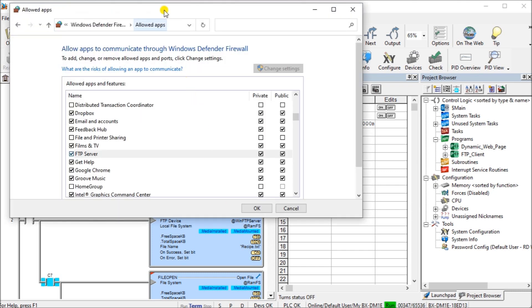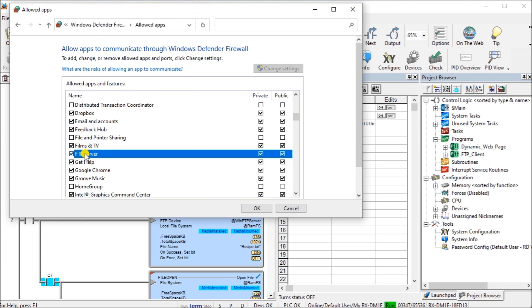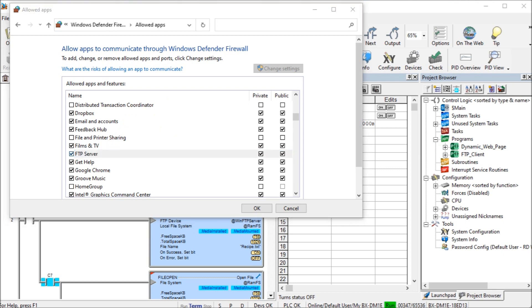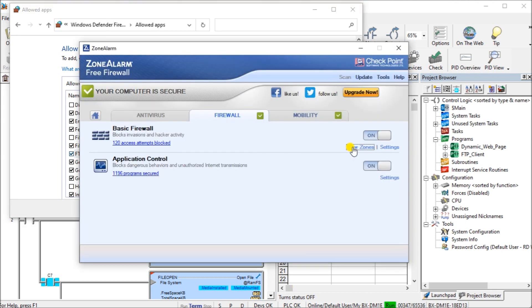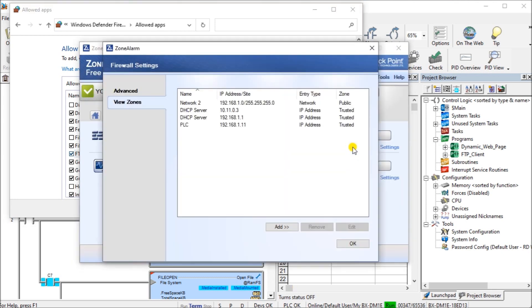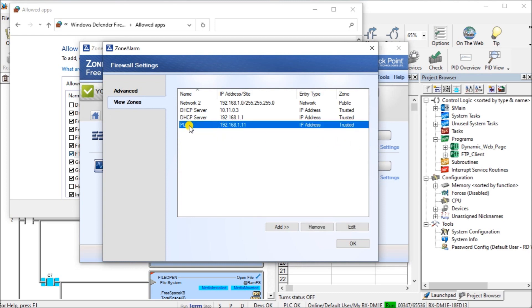If we look at our windows defender, you can see if we look under the allow apps, you will see a setting called FTP server. It must be selected private and public and enabled so that it will allow that app to actually operate on our system. If we have a program like I do like zone alarm, we want to view our zones and under our firewall, we're going to allow our PLC at 192.168.1.11, which is our BRX Do-more PLC location as a trusted site. That way we can move information in and out of that FTP server.